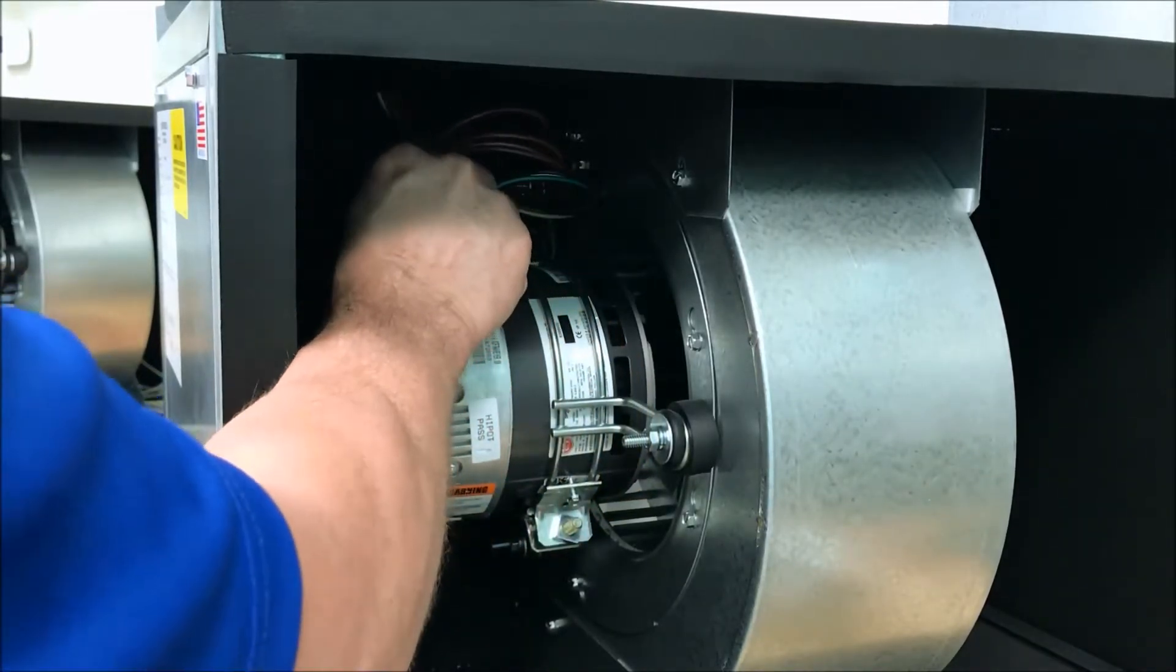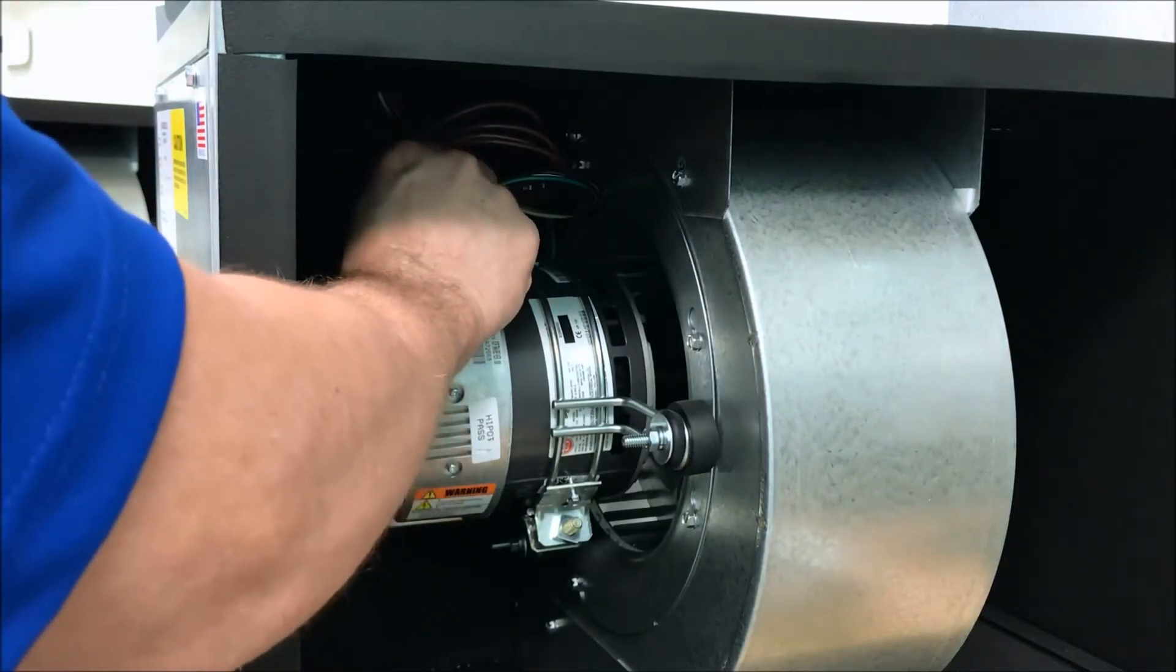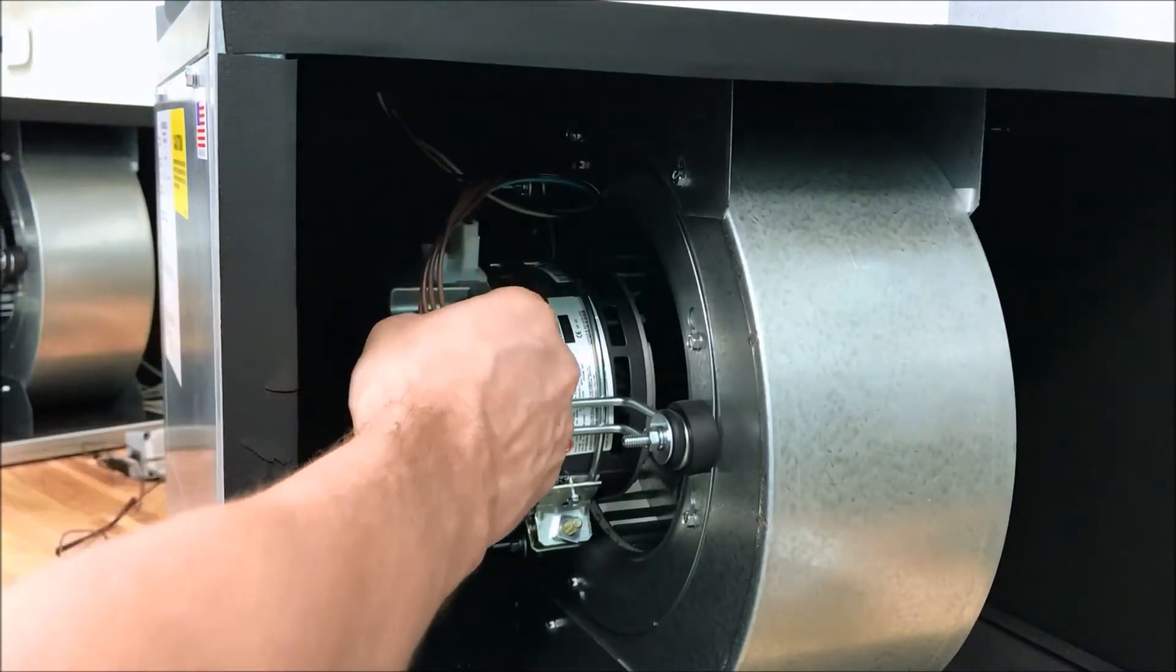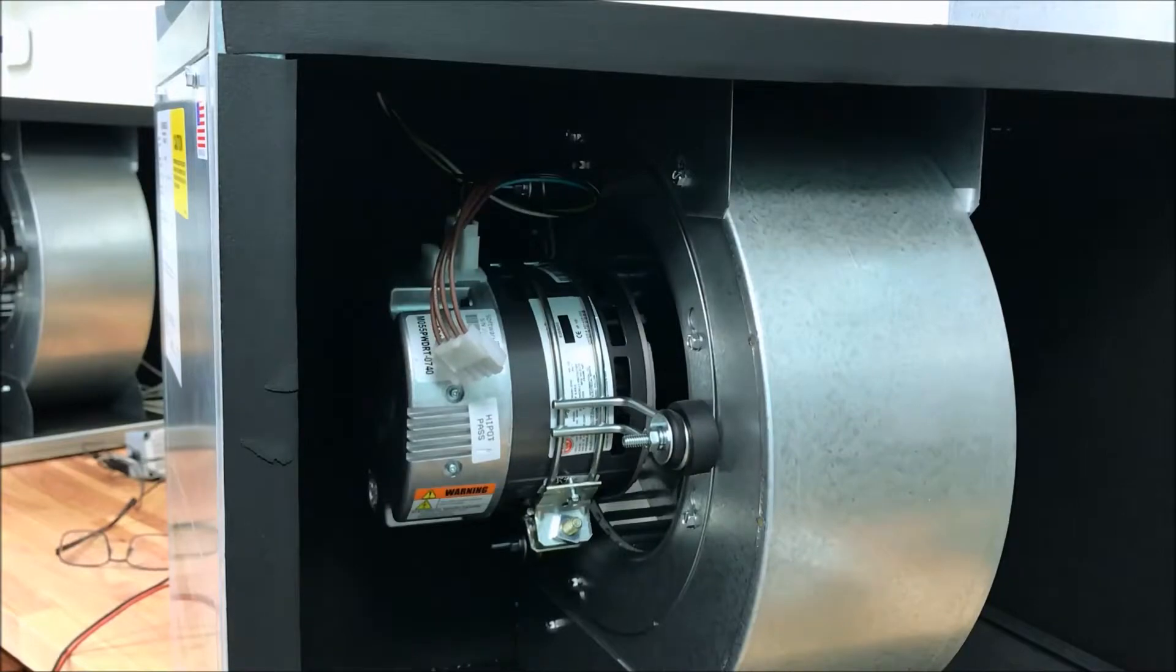Apply 24 volts to these wires as this is plugged in. The motor goes into a test spin. If the motor does not spin, replace the motor. If the motor does spin, then replace the board.